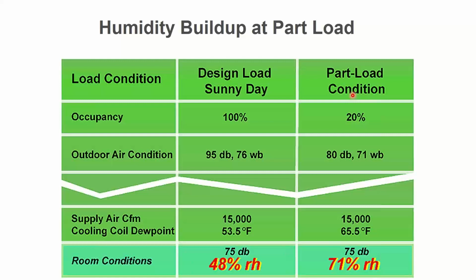However, if I have a part load scenario, meaning everybody doesn't show up, or it's not as hot outside, and I still run my 15,000 CFM like almost all the existing systems out there and small offices do, or retail or whatever, I end up with an average dew point of around 65 because the stat's going to satisfy and shut off, and then it's going to run and shut off and run and shut off. So I'm going to have 50-degree dew point, then I'm going to have 72, then 50, then 72, and on average I might get 65.